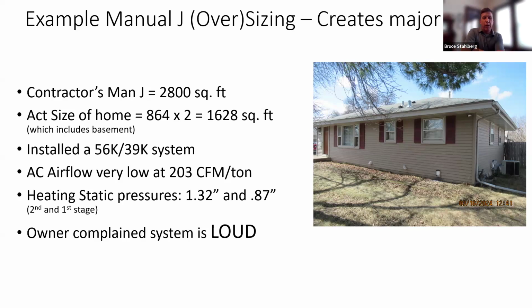Sorry about that. The airflow was measured at 203 CFM per ton, which is very low. That would make a risk of the coil freezing up. But more importantly, the static pressures on the heating side were 1.32 and 0.87, which was much higher than the manufacturer wants. And then again, the owner complained that it was loud. We did go back and adjust this one and made it right, but that's something that we caught on the contractor's Manual J.